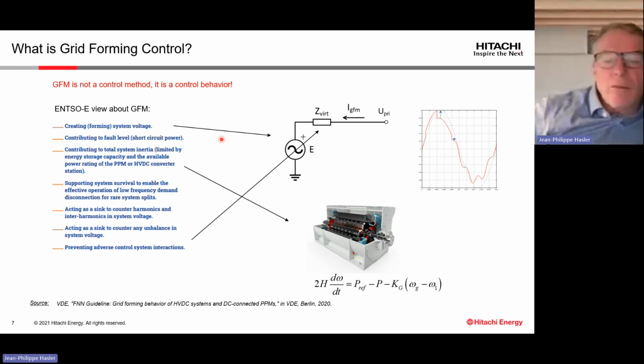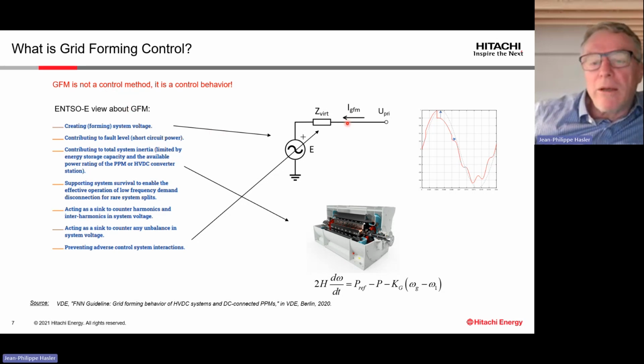Now, just to compare a little, what is the difference with grid forming, the way we want to implement it for our STATCOM, and a generator? Finally, the difference between the two is really small, because a generator is a kind of voltage source, controlled by the swing equation, mainly the phase angle, and you have an impedance. That impedance can be seen as equivalent to the synchronous impedance.